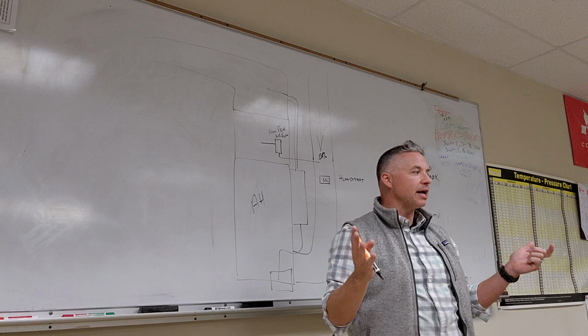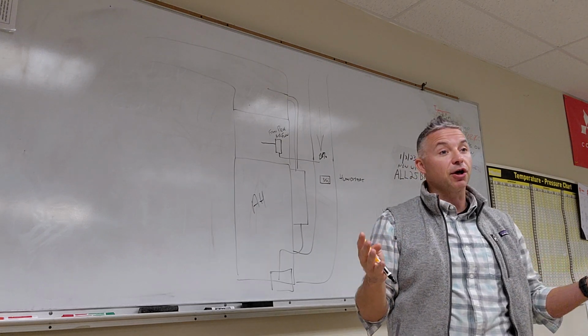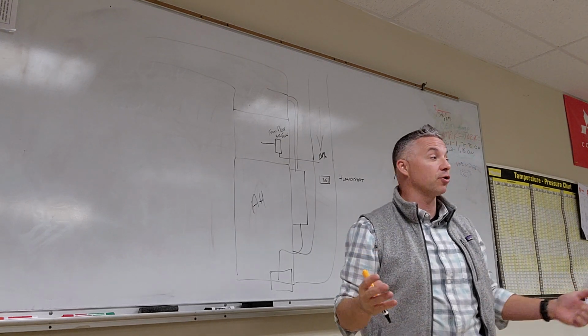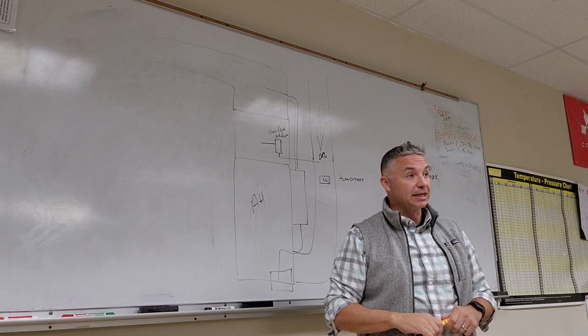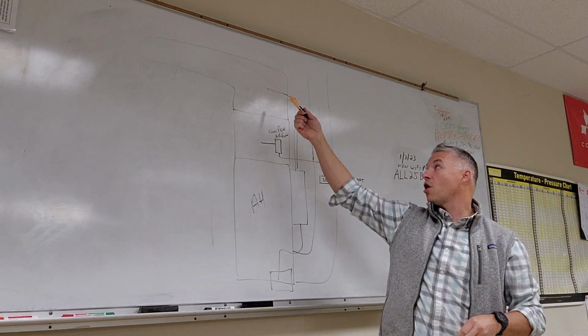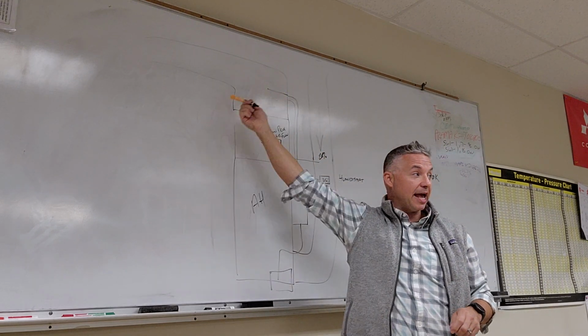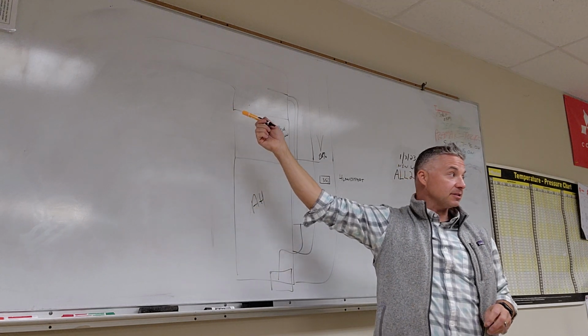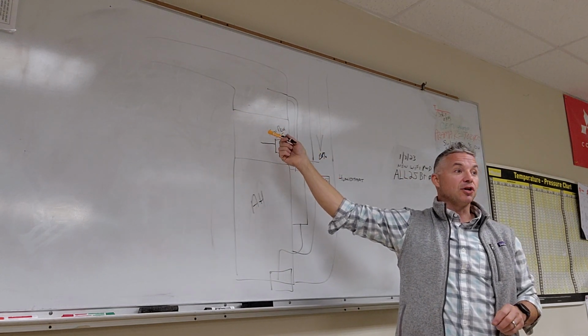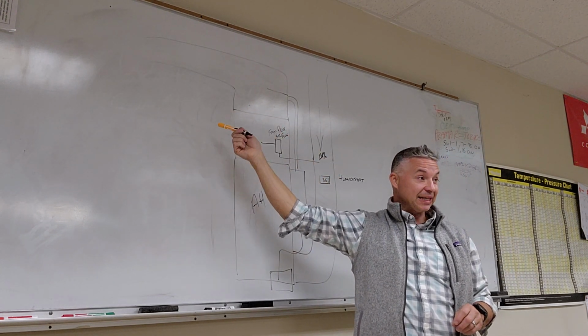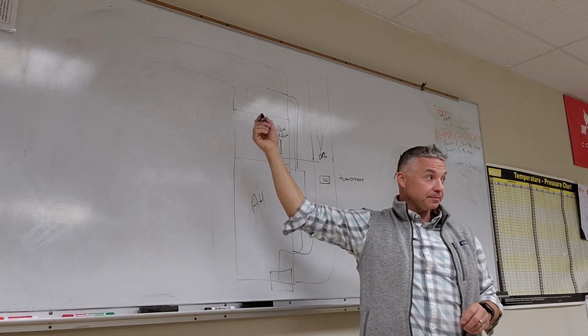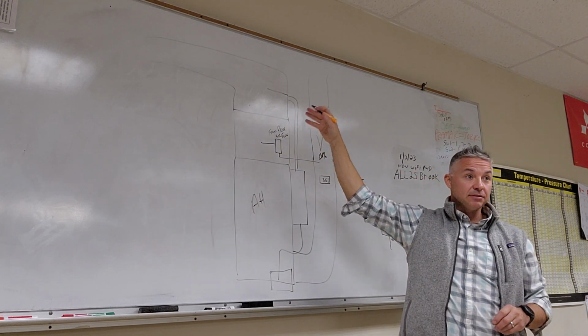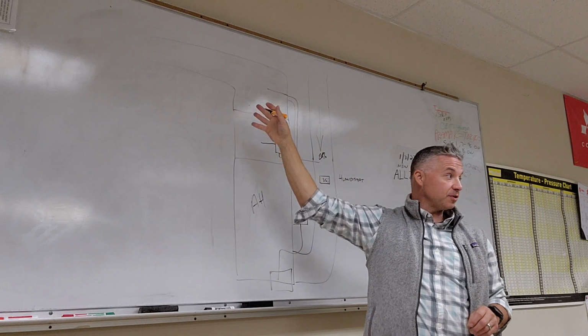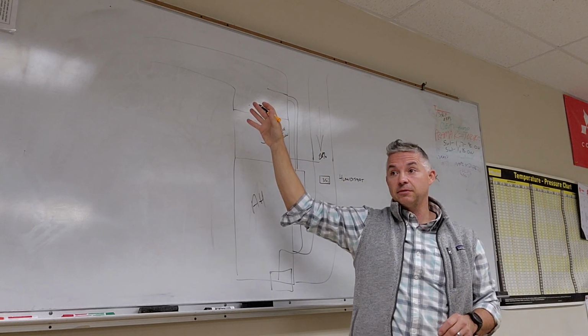On an Aprilaire, there's not really any harm in keeping that thing running other than the noise it might be making or you're wasting some water. But on a steam unit, if we were to be pumping raw steam into that ductwork without a fan actually working, we're making a mess. We're damaging ductwork if it's internally insulated, right? And moist, dark is a recipe for mold. Okay?